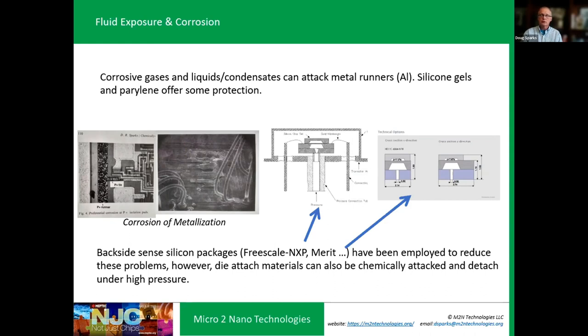If you were exposing the pressure sensors to, say, the air intake manifold in an automobile, some companies like Freescale, which is now NXP, and Merit started looking at backside sensing, so that the fluid only hits the bottom side of a silicon diaphragm. Or for some of the flow sensors I used, you only hit the bottom side, or an internal silicon tube or microchannel. So those are ways that people have come up with unique packages, designs, and unique materials to limit corrosion of electrically active and corrodible materials in your sensors.